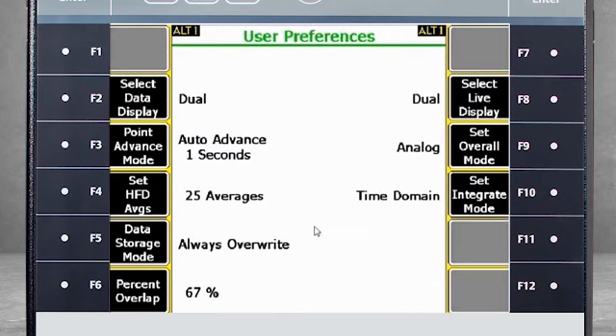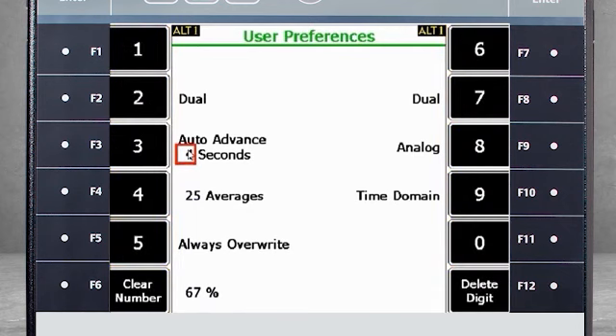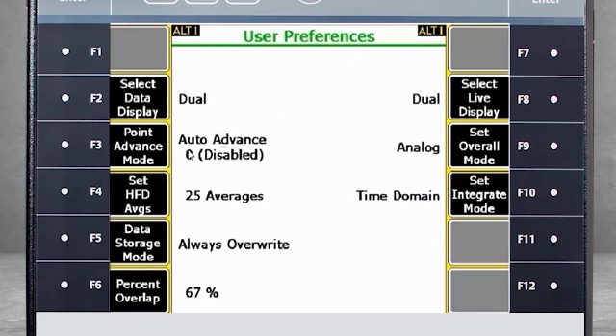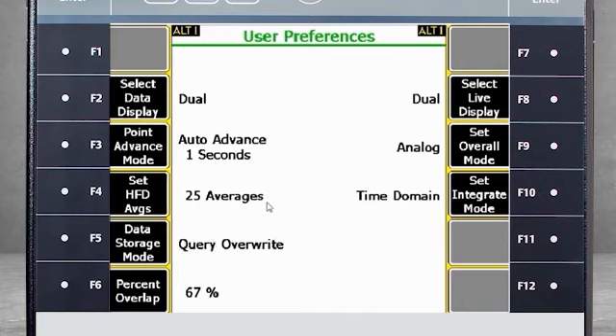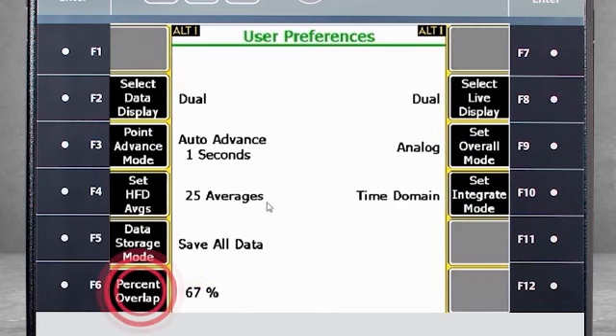F3 Point Advance Mode sets the length of time the data will be displayed before automatically jumping to the next point. It is currently set to 1 second, but if I change it to 4 seconds, we'll have more time to see the data before moving on. If you set the Advance Mode to 0, you disable Auto Advance and will have to manually advance to the next data point. F4 sets the number of high frequency detection averages collected — 25 averages can be collected very quickly with the AMS 2140. F5 Data Storage offers three options: overwrite data already collected, query whether to overwrite or add to stored data, or save all collected data. 67% for overlapping averages is typical, but you can change that using F6.